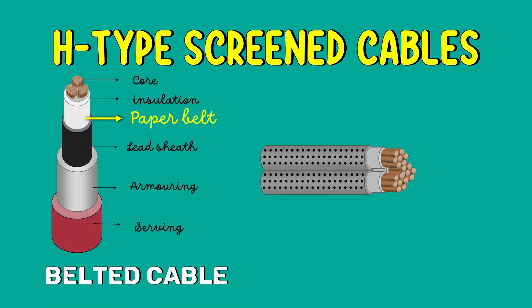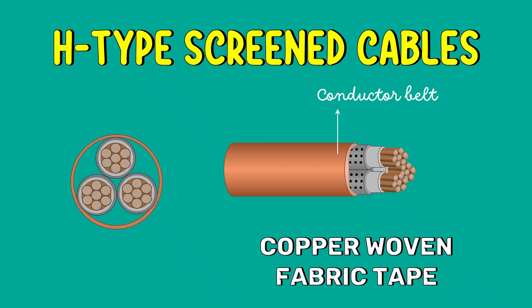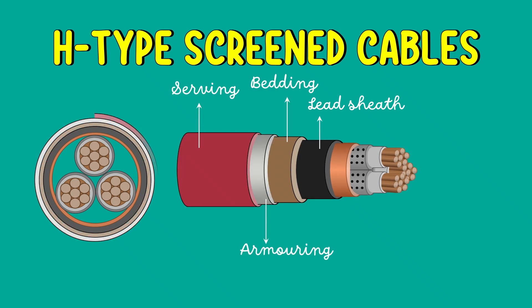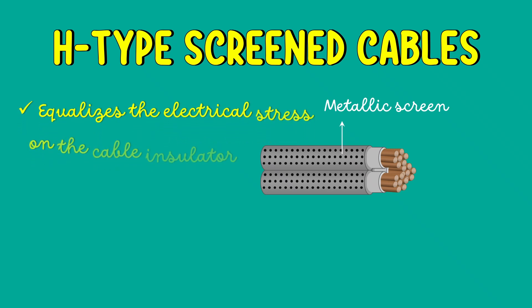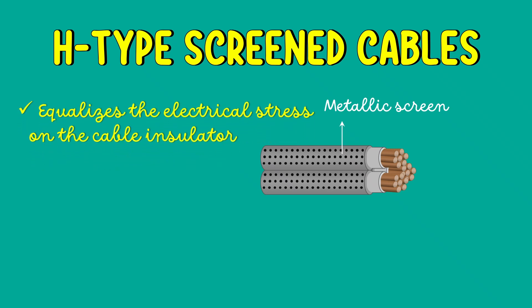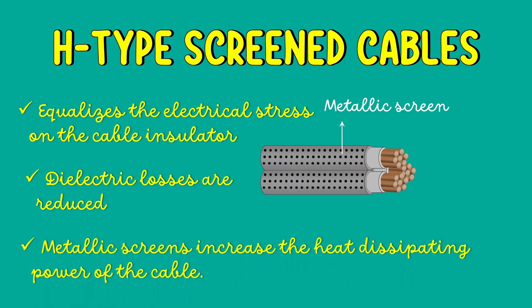The cores are laid so that the metallic screens make contact with one another. Instead of a paper belt, H-type cables have a conductor belt, usually a copper woven fabric tape. This is followed by a lead sheath, bedding, armoring, and serving. The presence of the metallic screen equalizes the electrical stress on the cable insulator, reducing dielectric losses. Another advantage is that the metallic screens increase the heat dissipation power of the cable.